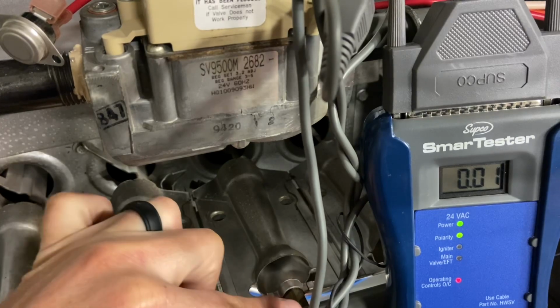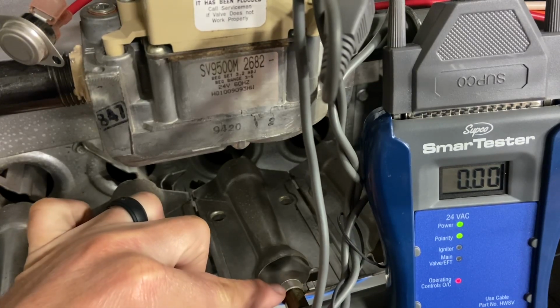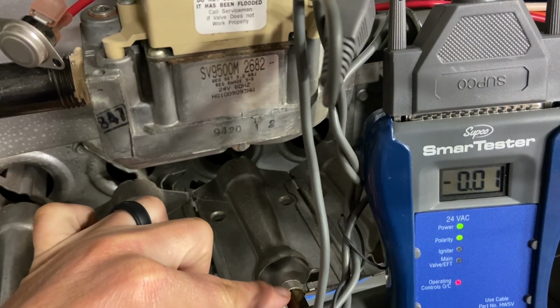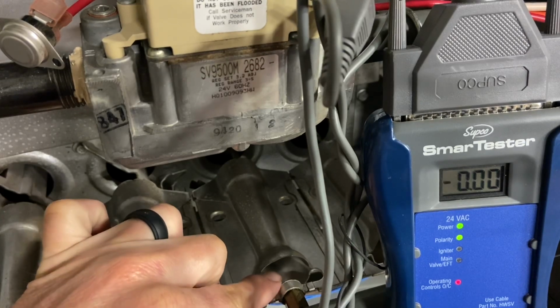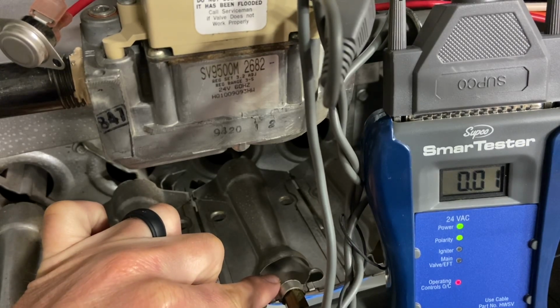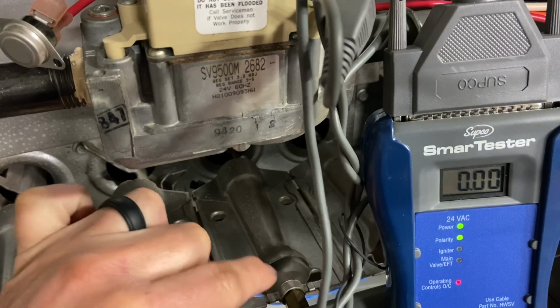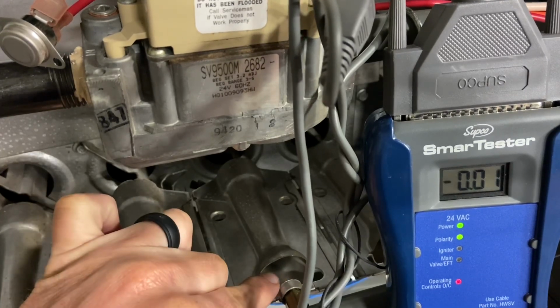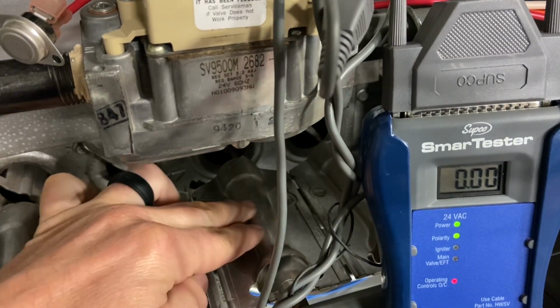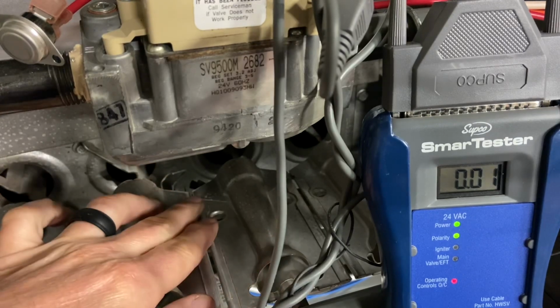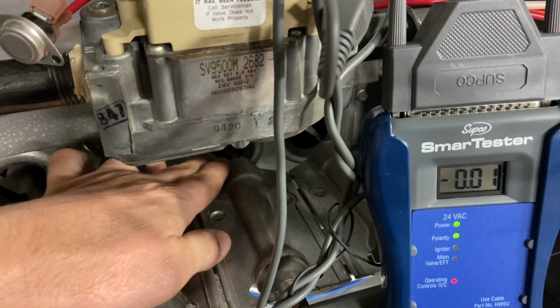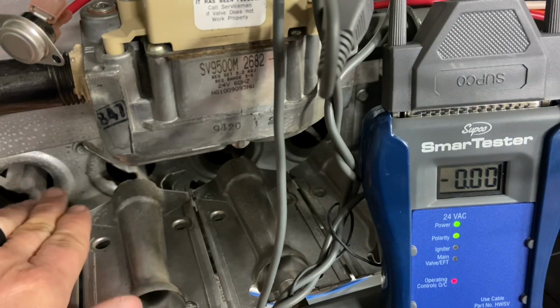So the manifold delivers gas to this component called the spud, and the end of that spud is a hole called an orifice, so it shoots the gas into the center of this in-shot burner. We just simply call them jets. It mixes with primary air. The air is being pulled in here, so the burner's job is to mix the air into fuel. It's going to go across the pilot, igniting into a flame that's burning inside of this heat exchanger.